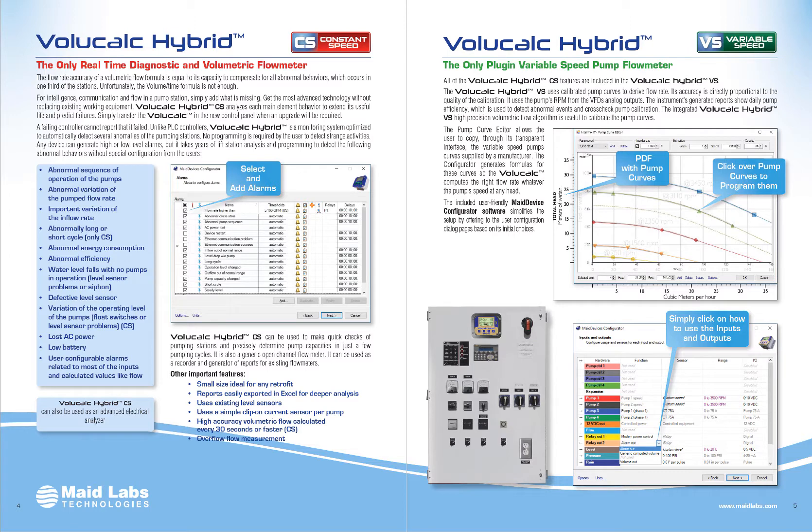Volucalc Hybrid is a volumetric flow meter. Why do you want to know flow in the station? Because when you have flow and when you have power consumption, you're able to calculate the number of gallons pumped per watt of electricity. It's like the number of miles per gallon in your car. If you're doing 50 miles per gallon, it's not important. If your car goes down to 2 miles per gallon, it just became important.